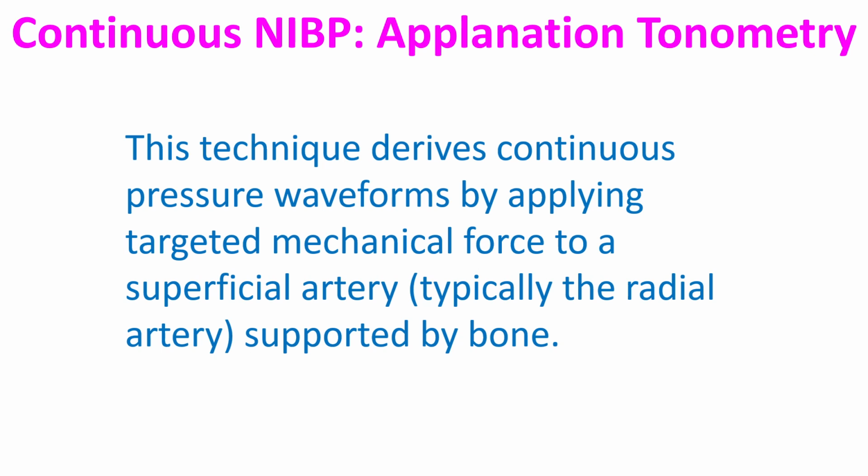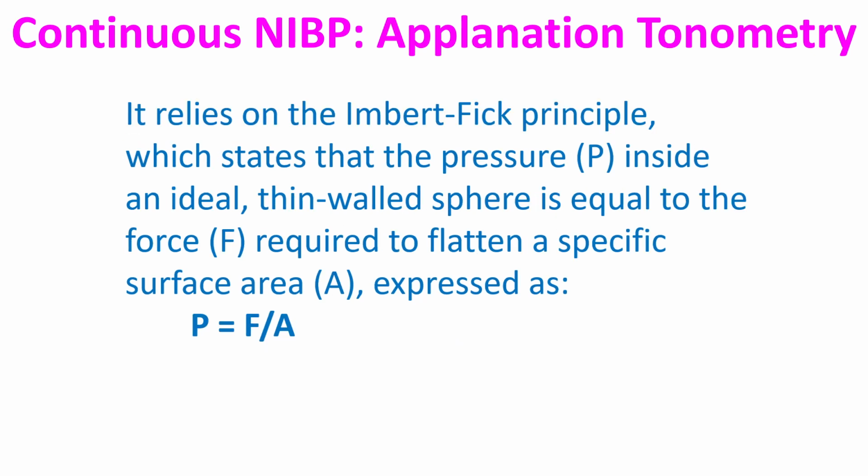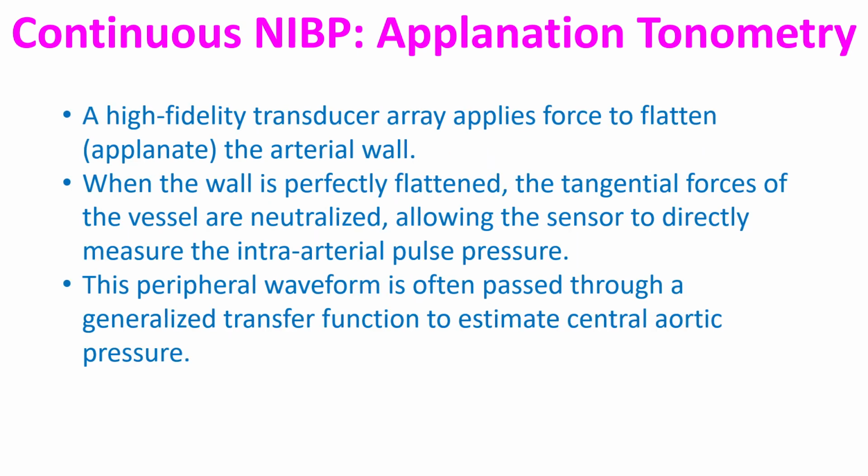This technique derives continuous pressure waveforms by applying targeted mechanical force to a superficial artery, typically the radial artery, which is supported by bone. It relies on the Imbert-Fick principle, which states that the pressure inside an ideal thin-walled sphere is equal to the force required to flatten a specific surface area, expressed as P = F/A.